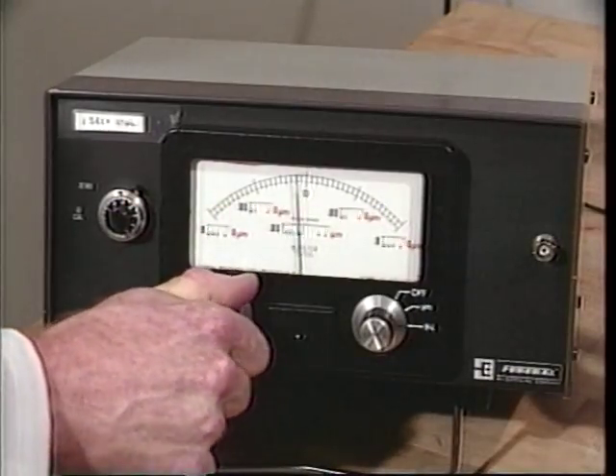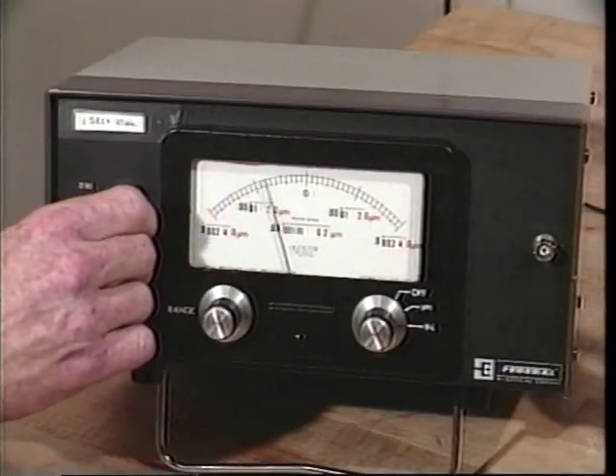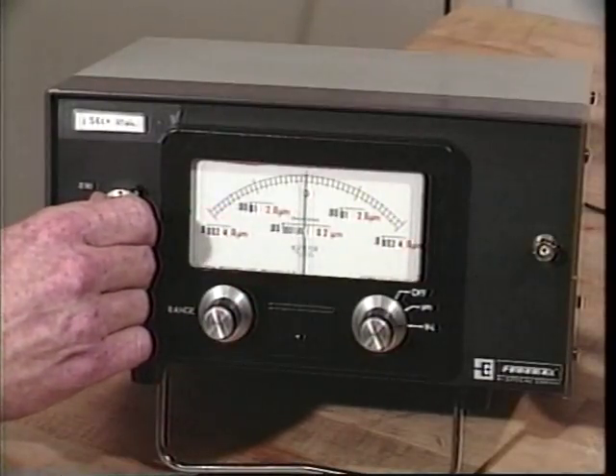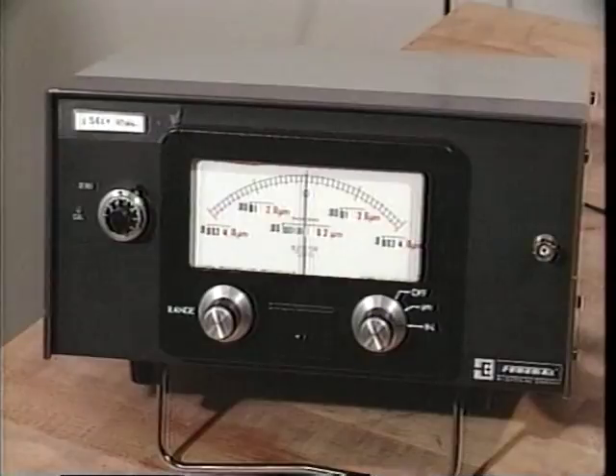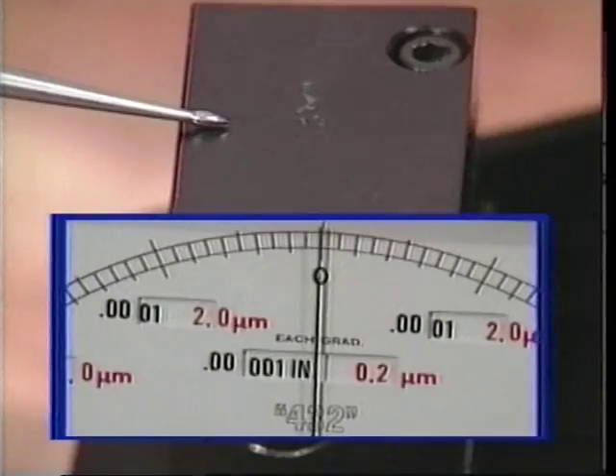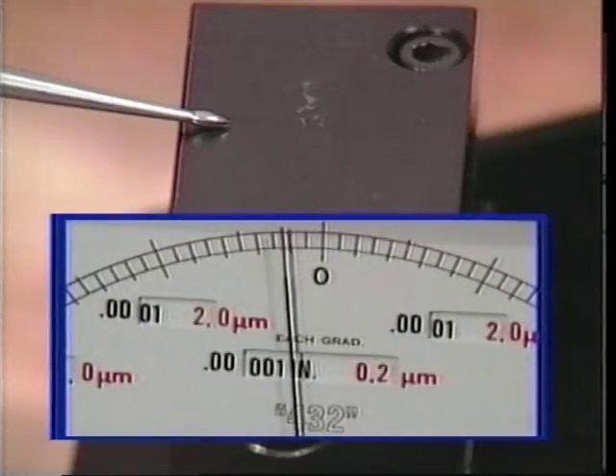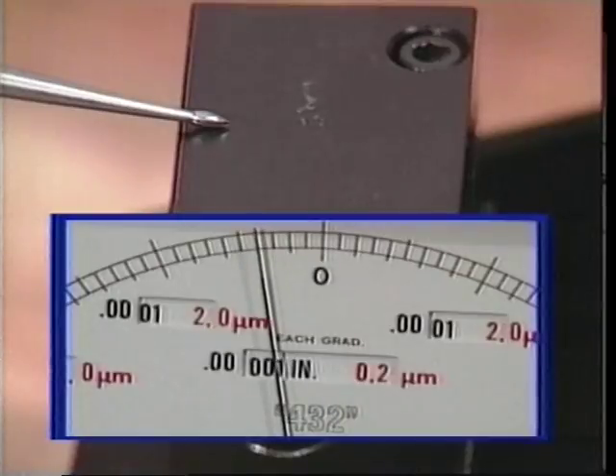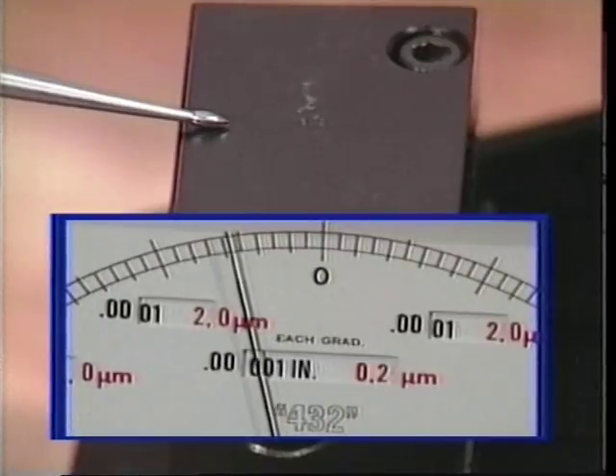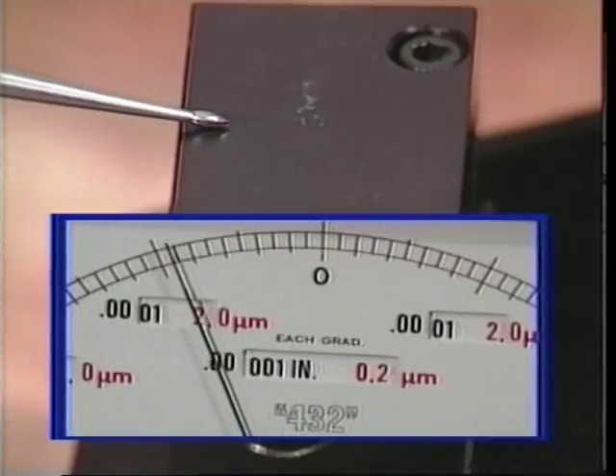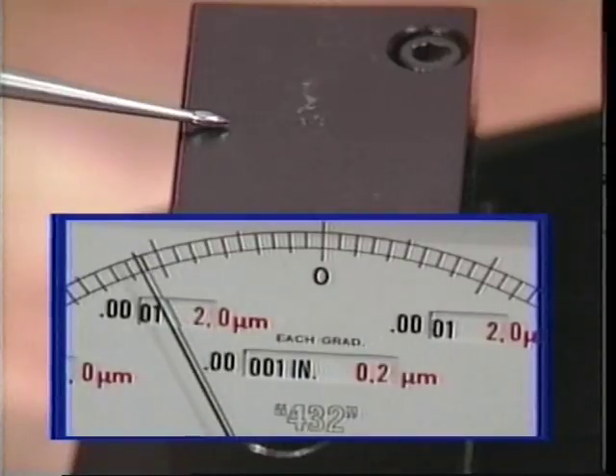If another range is desired, switch to that range, and if necessary, use the electronic fine adjust knob to re-zero the display. The position of the measurement surface relative to the stylus may now be varied, with the variation being displayed by the indicator gauge meter or the analog voltage output.